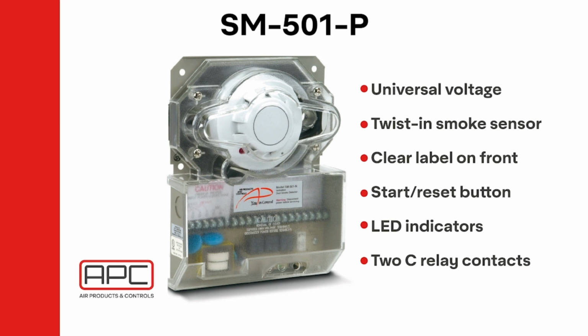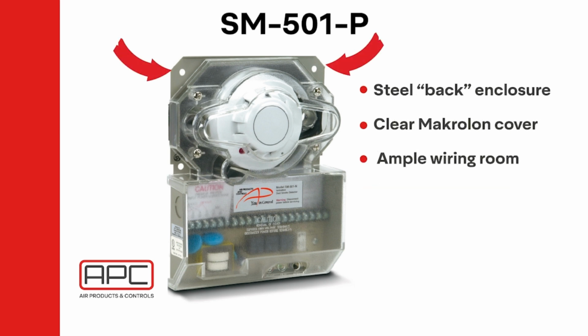The LED indicators on the board are the same easy to understand as the SL2000 detectors. Red equals alarm, green equals pilot, and off equals trouble. This series has a steel back enclosure with a clear Makrolon cover. The SM501 features 2 C contacts and ample room for wiring.